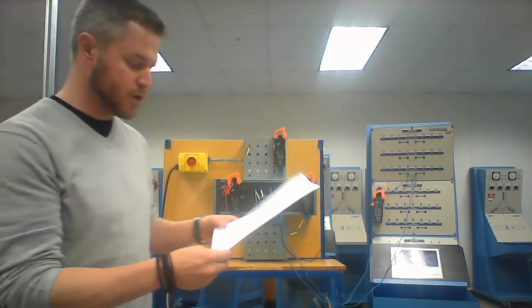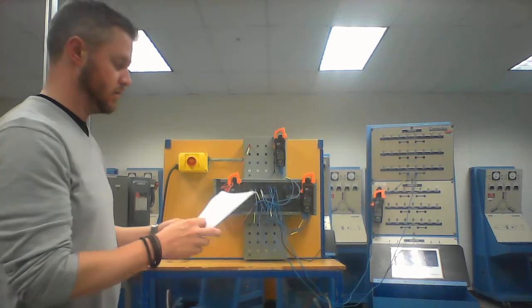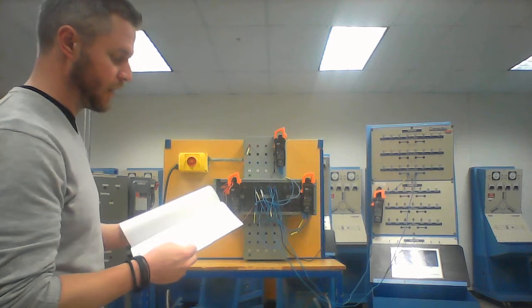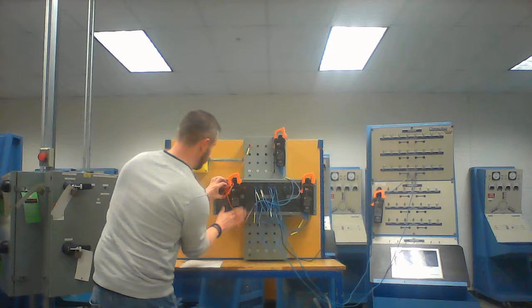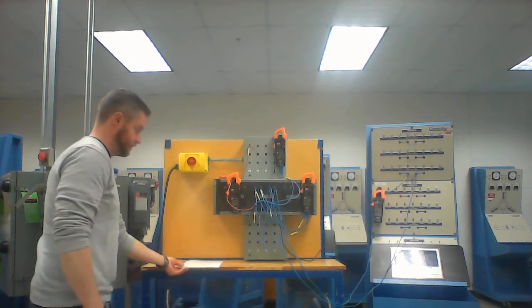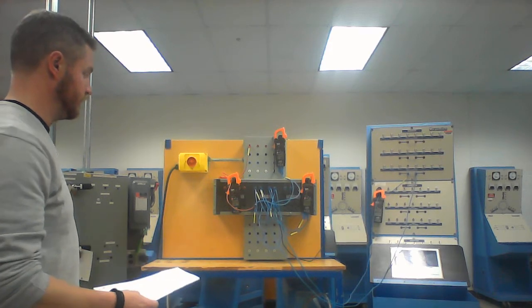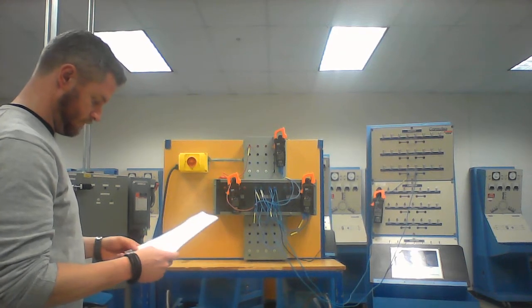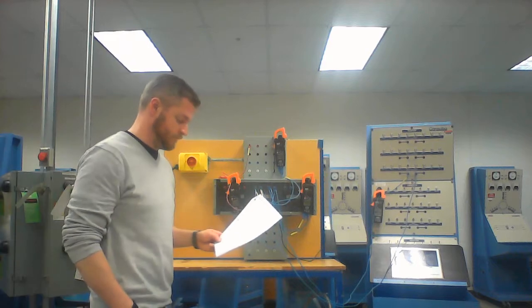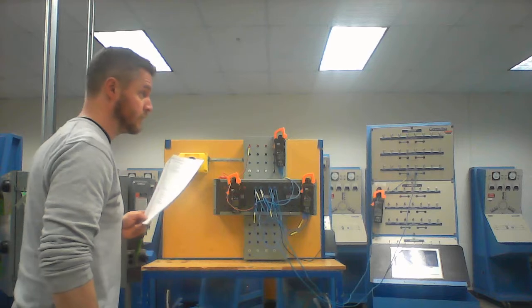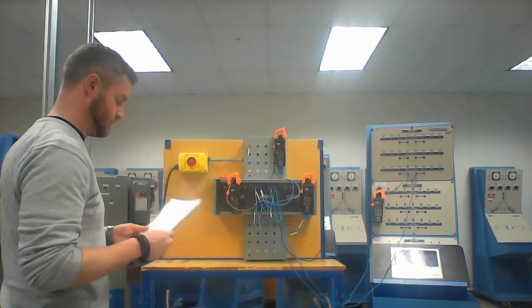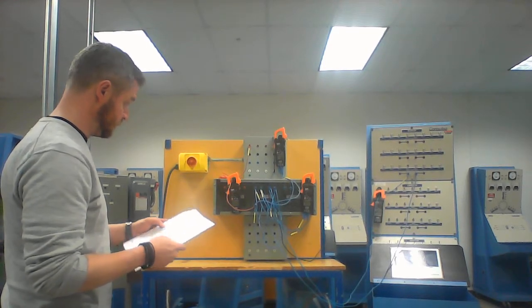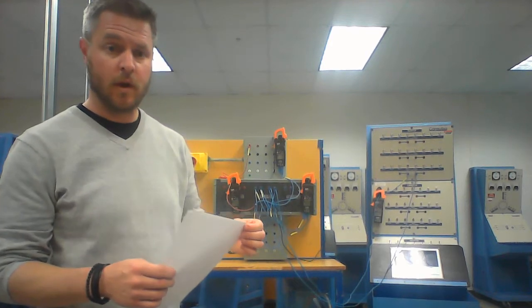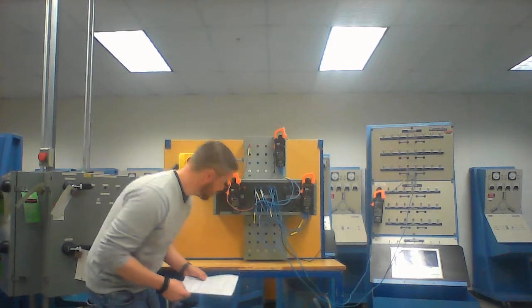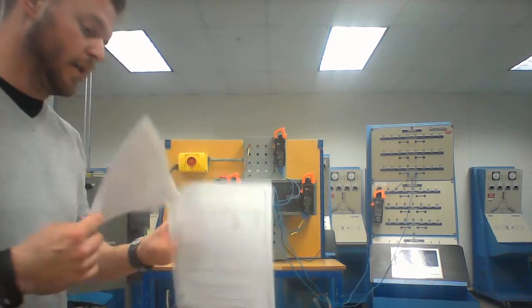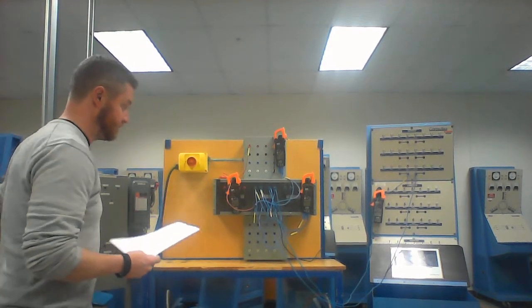Calculate the primary current using the voltage ratio. Be sure to add in the excitation, and measure the primary current and compare it to the calculated value. Plus excitation. I get 0.636 plus 0.144, 0.78. And my meter is reading 0.75. Pretty close. All right. So step number 20, the meter is reading 0.75 amps primary current.